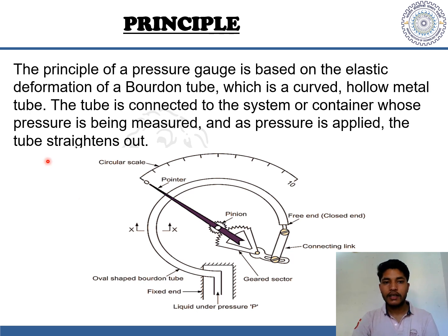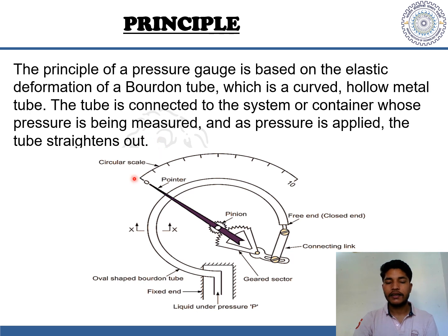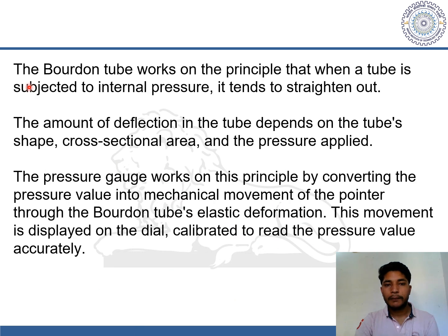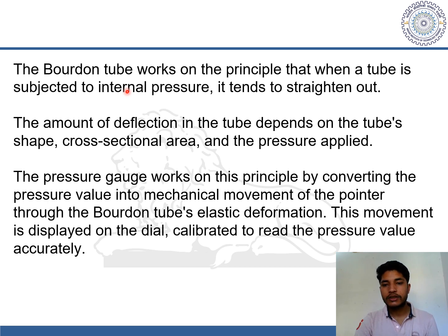The principle of a pressure gauge is based on the elastic deformation of a Bourdon tube. The tube is connected to the system or container whose pressure is being measured, and as pressure is applied, the tube straightens out. We can see it in the diagram too. The Bourdon tube works on the principle that when a tube is subjected to internal pressure, it tends to straighten out.